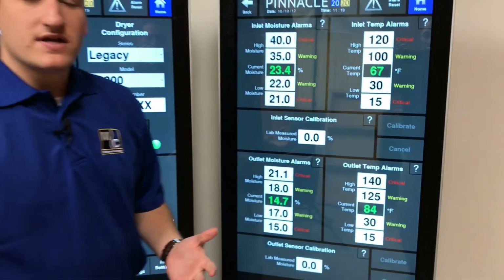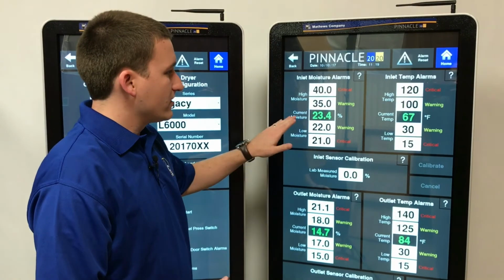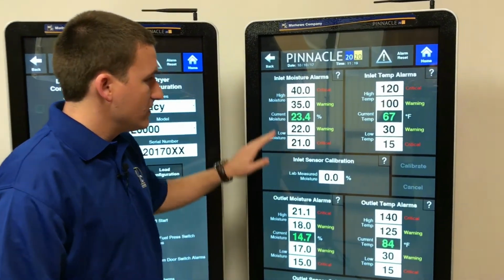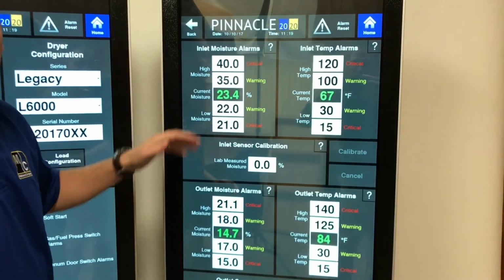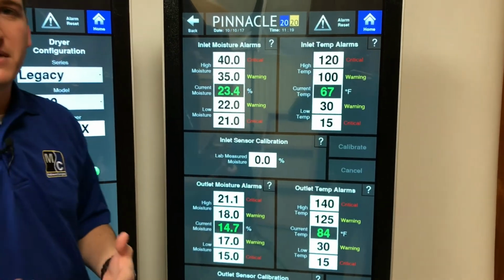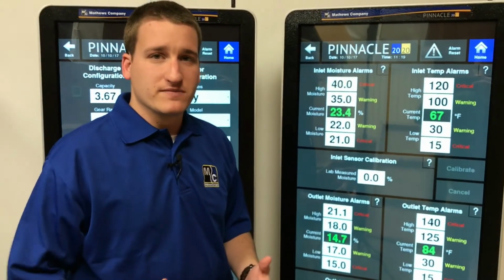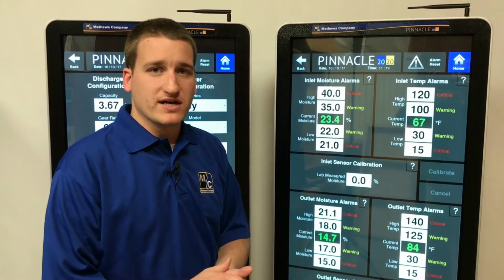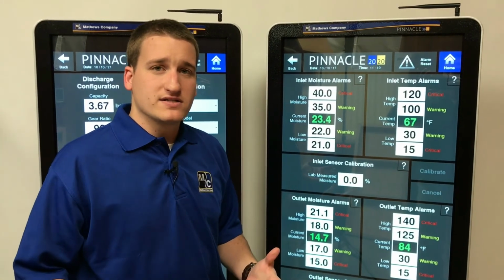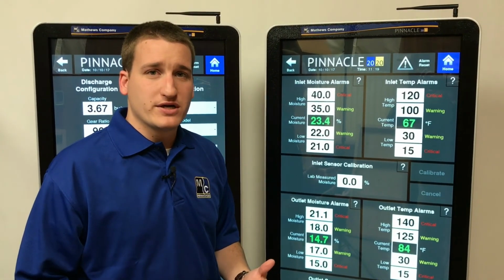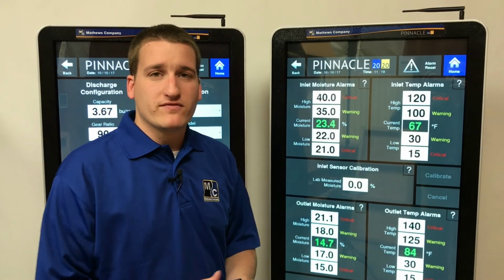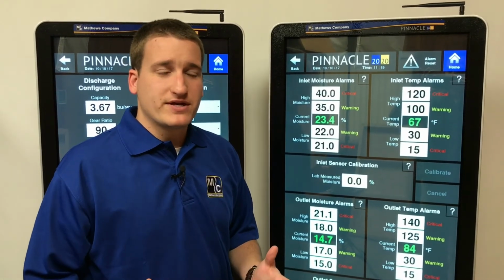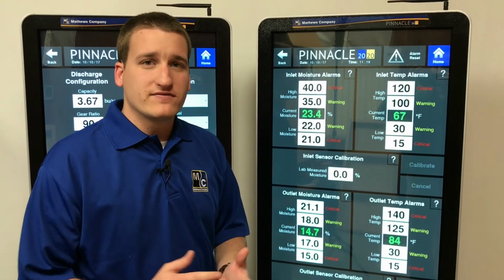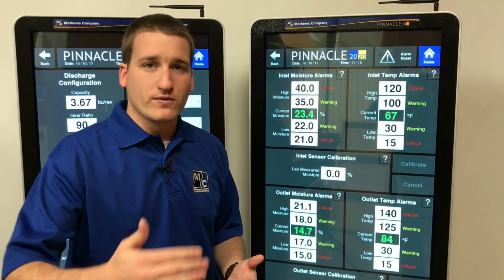A couple of notes that I want to make on here. The current values that you see here are 3-minute averages. So they won't update immediately upon finishing your calibration. They'll take a couple minutes for them to approach that value. And the second note is that the most we can change a sensor calibration in one shot is 0.5%. So if your sensor is reading off by more than 0.5%, you'll have to do multiple calibrations to get all the way to where you need to be.